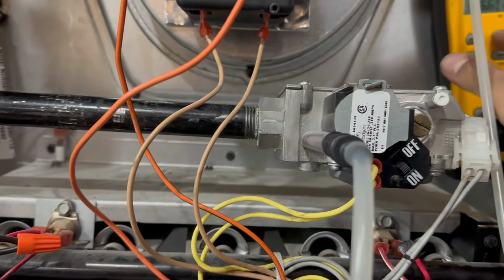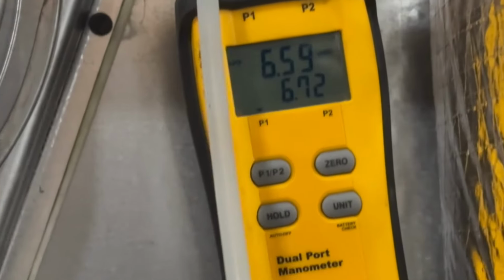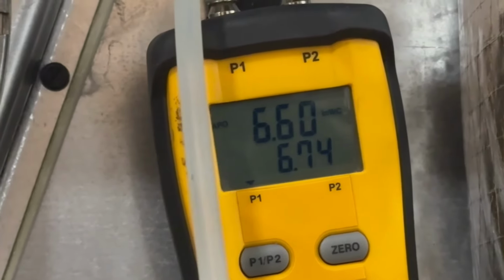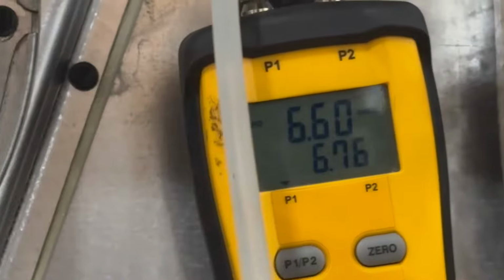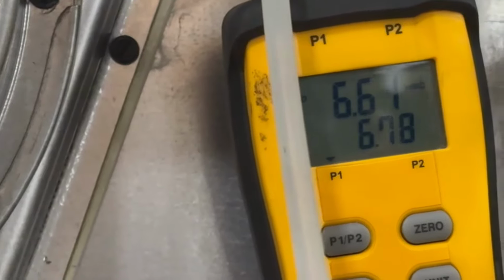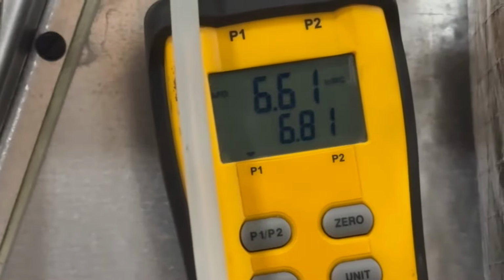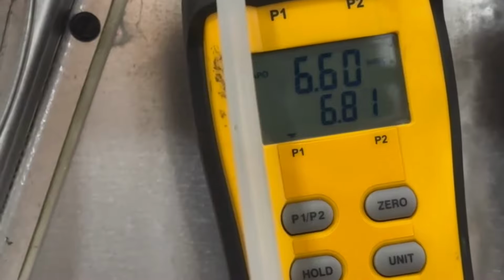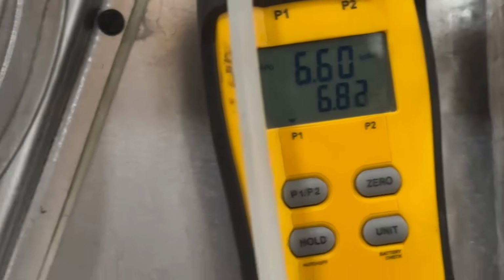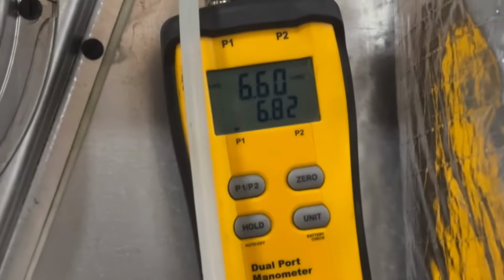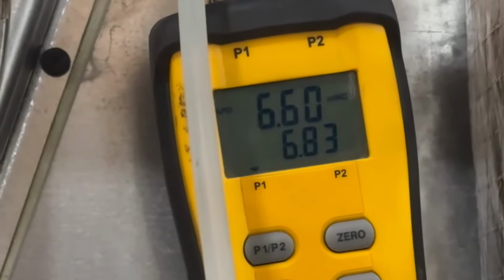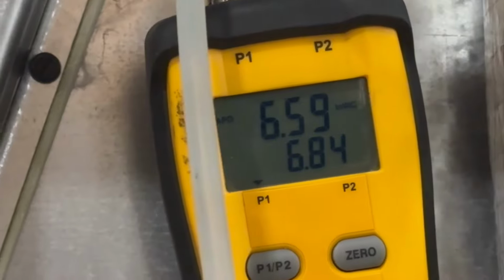Push that in. And I am reading 6.59 inches of water column. So I did say 8 to 11. Even if you read 7 to 12 or 6.5, they'll still work. But I'm reading 6.60 or close to 7 inches of water column. So that tells me that I am getting incoming gas pressure to the unit, to the system. Okay. So that's the first step.